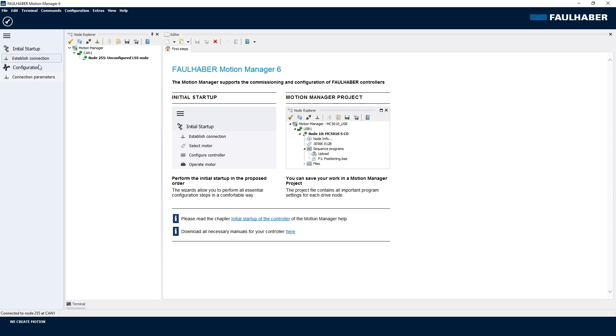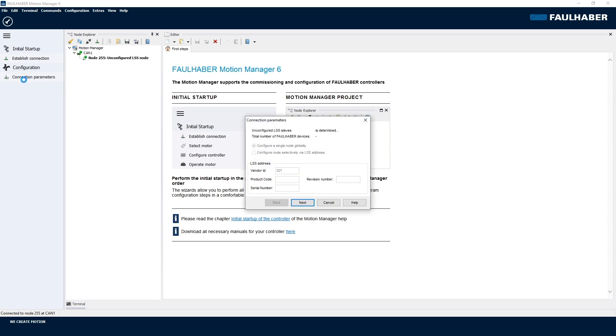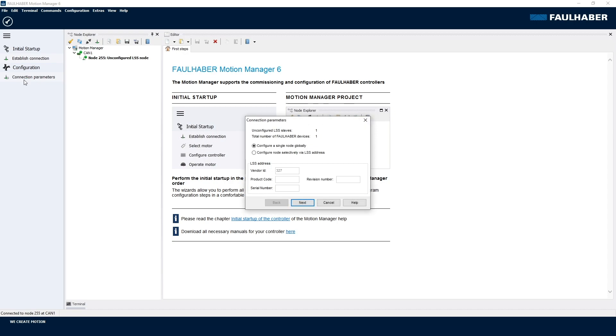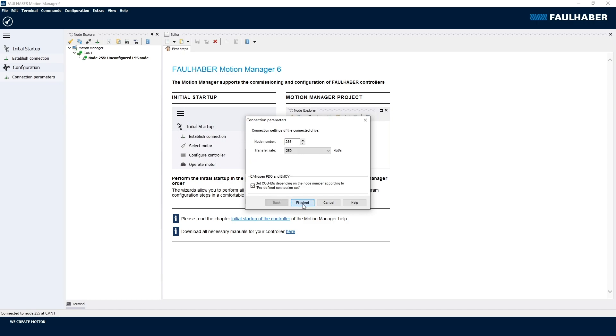The tools are populated here, and the only tool available is the one for the connection parameters. That's used to now assign a valid node number and the baud rate that I want to use. In that case I can use the version where I have to configure a single node globally. If it would be a network of these nodes, I would have to add the product code and serial number of my device. That's on the sticker on the back of the motor.